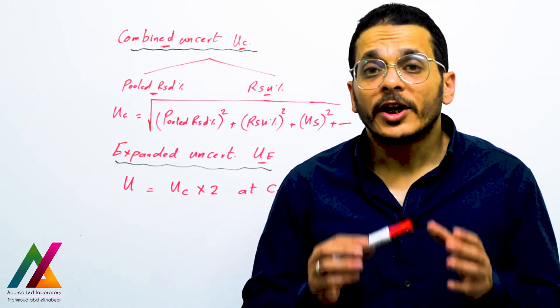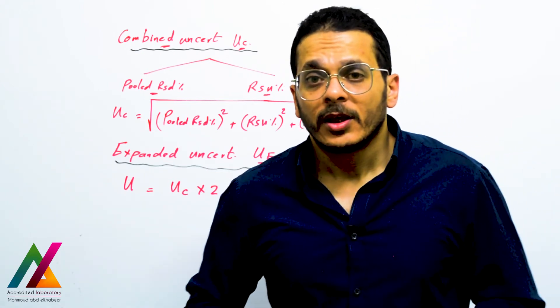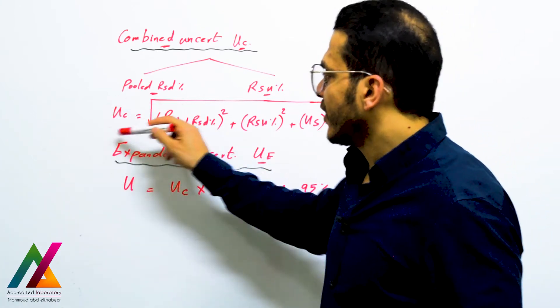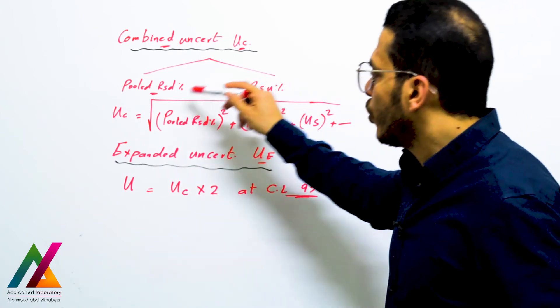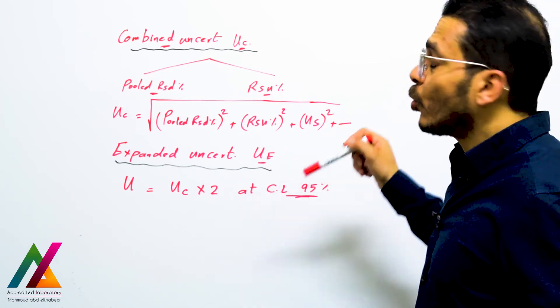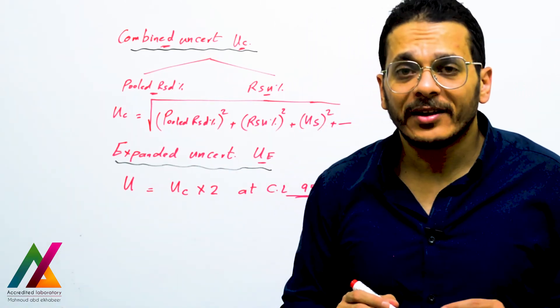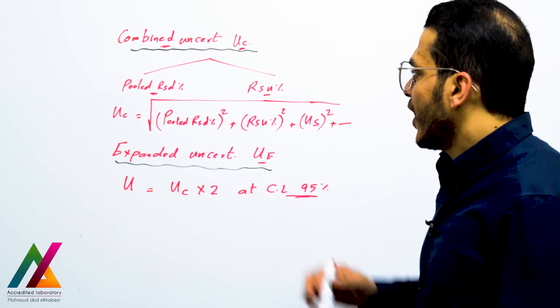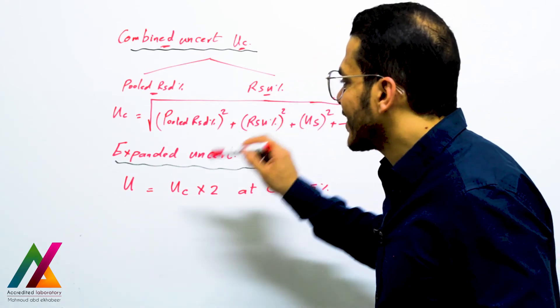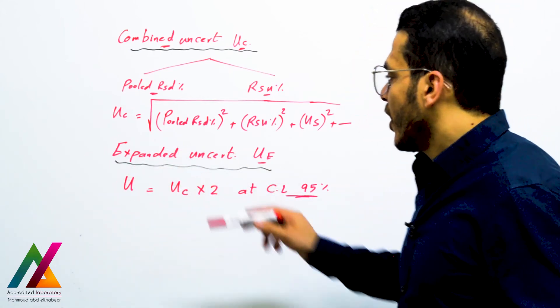Then you calculate the combined uncertainty, where individual uncertainties from each source are combined together to get the overall uncertainty. From Type A evaluation, the combined uncertainty equals the square root of (pooled RSD² + relative standard uncertainty²). If you are responsible for sampling, the sampling uncertainty should also be added. After calculating combined uncertainty, calculate the expanded uncertainty, which is the overall uncertainty at a 95% confidence level.